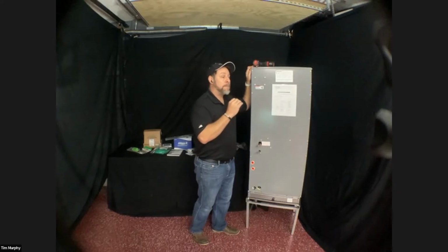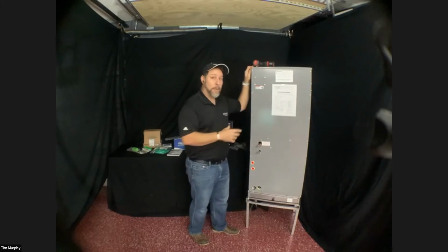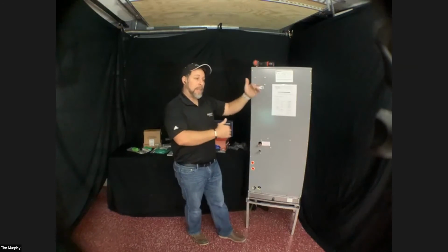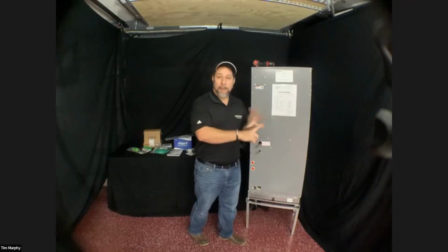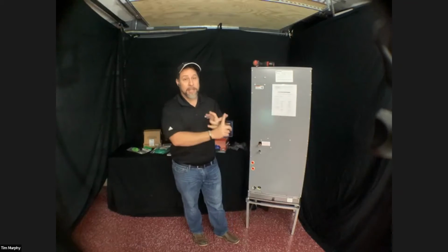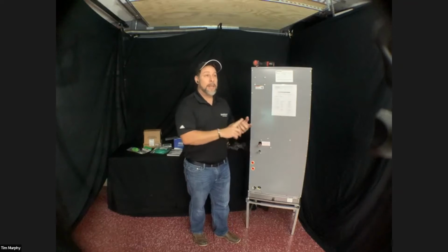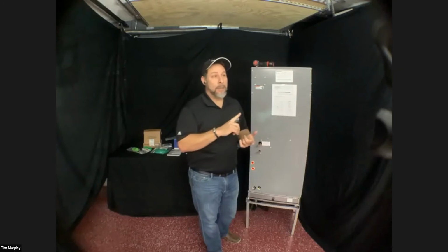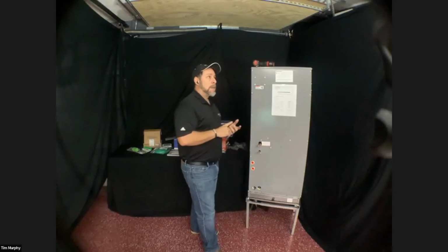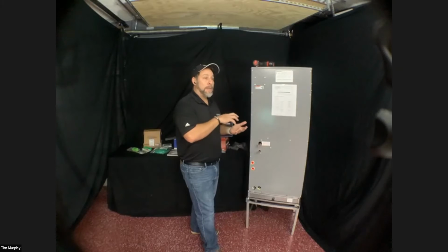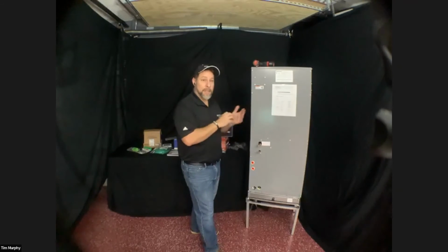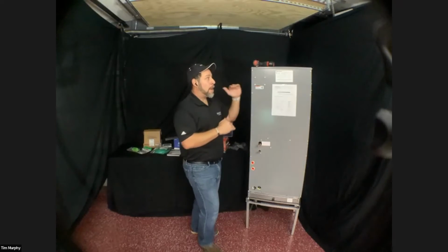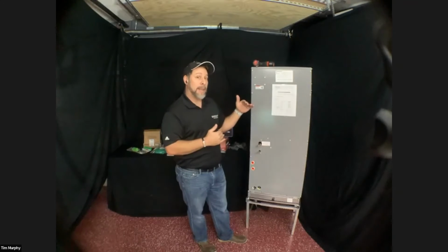It'll give you all your optional equipment. The first page breaks down the copper sizes, how much is pre-charged, and if you need additional Freon, how much you'll need per foot. It covers heating and cooling capacities and the different control options for each system. If you're not sure whether an air handler matches a certain condenser, it'll give you a list of matching condensers or air handlers.